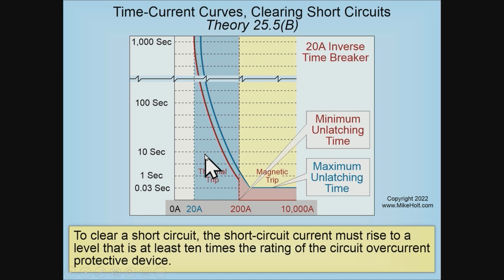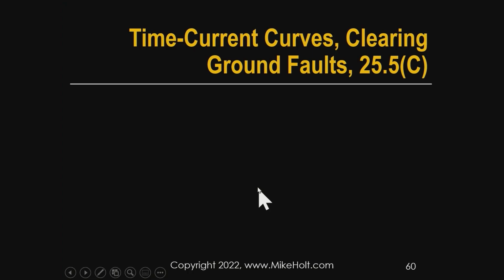Once it reaches the instantaneous range, so here's an example, and we probably need to maybe not put 200 amps here because we don't know if it's going to be 200 amps. But there's a little slightly different. So here, the blue here is the thermal because it's not going to trip instantaneous. And then showing the yellow over here, that's when you get into the instantaneous, and we don't know how many times it is to get to instantaneous, but when it does get to instantaneous, then it can trip at 0.01 of a second. We're going to go down here. There. All right, I see that.